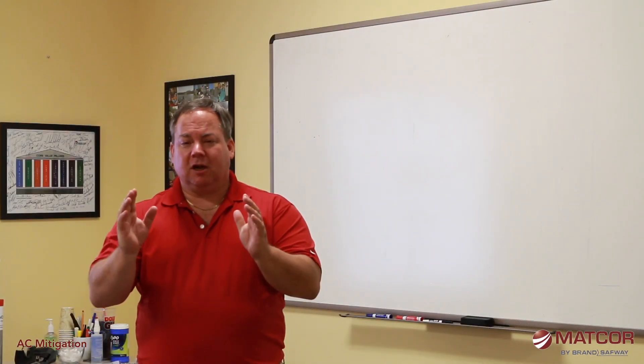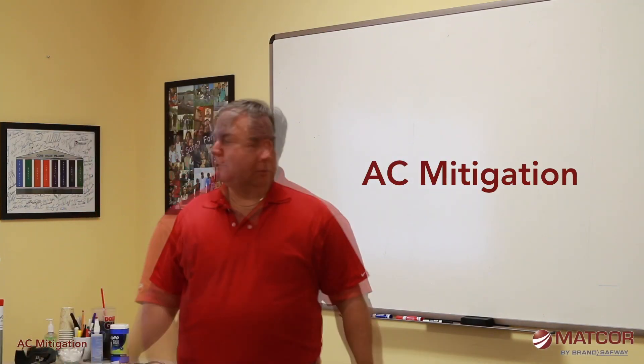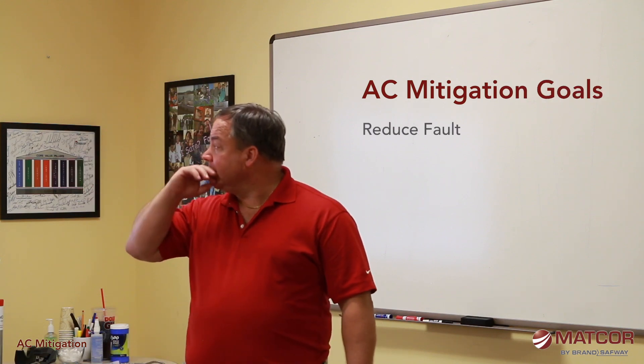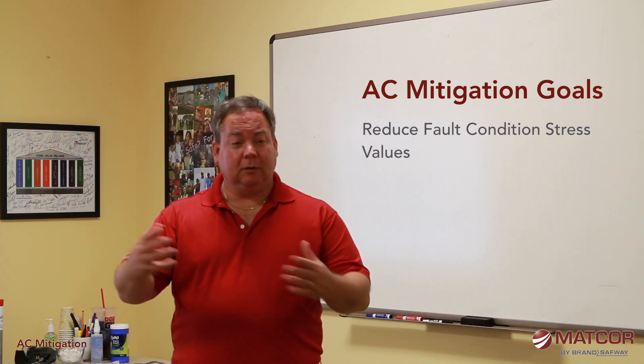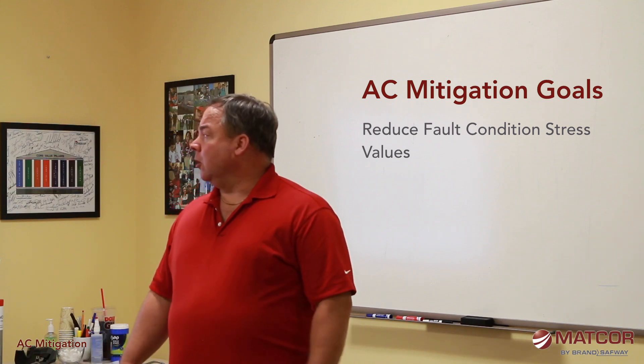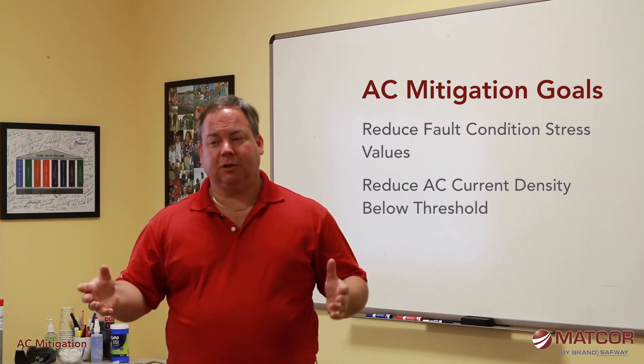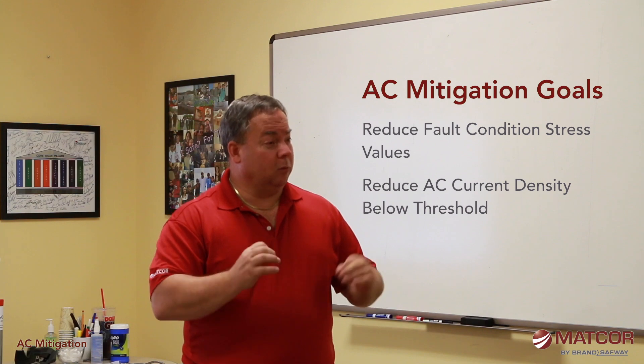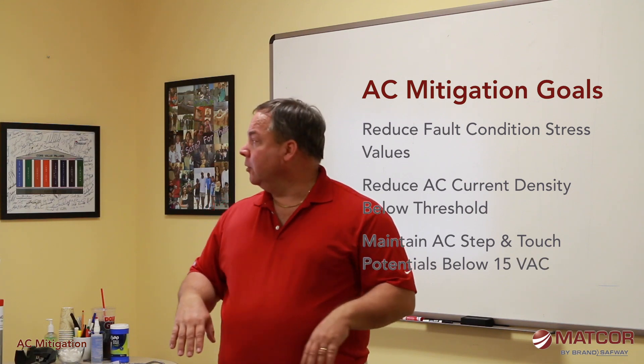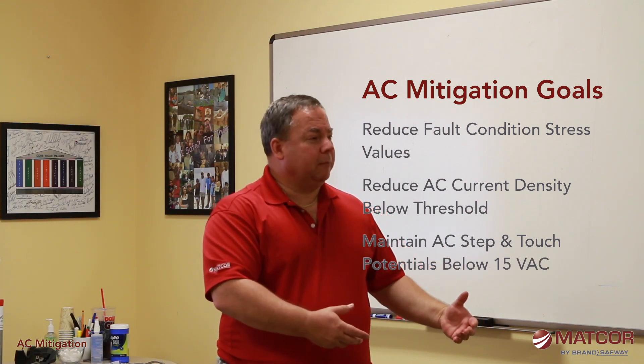We've talked about AC interference and AC modeling; next we're going to talk about AC mitigation. The goal for AC mitigation is to reduce your fault condition stress values to protect against coating damage and arcing potentials. Arcing is less frequent because you have to be really close to the pipeline. We want to reduce the current density below some threshold value — typically in the US we use 20 amps per meter squared for a one centimeter squared nominal holiday size — and to maintain AC step and touch potential below 15 volts so that people working in and around pipeline areas are not subject to shock damage.